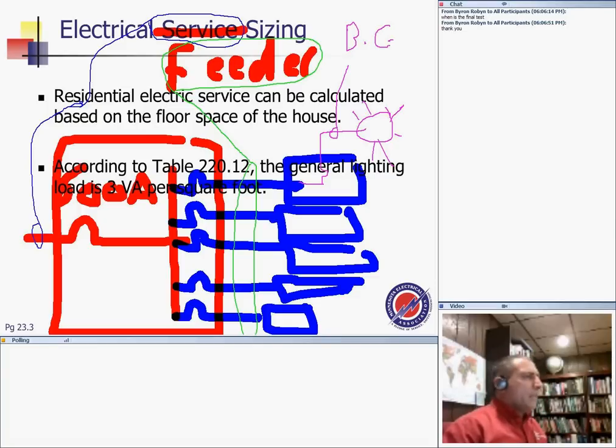So I say, guys, when I teach this topic, if you are in the electrical industry, the three most important circuits, and I believe I told you this before, are the service circuit, the feeder circuit, as well as the branch circuit. Branch circuits are the loads from the last overcurrent device to the utilization equipment, the load. The feeder is from an overcurrent device to another overcurrent device. And the service is from the utility all the way into your service entrance disconnecting means or overcurrent device.